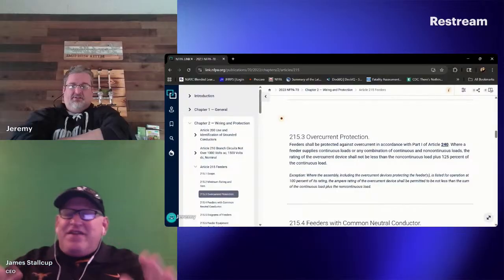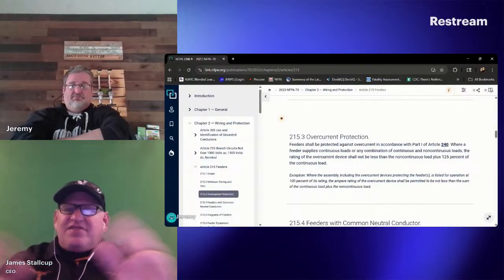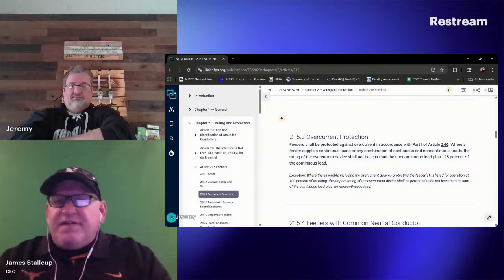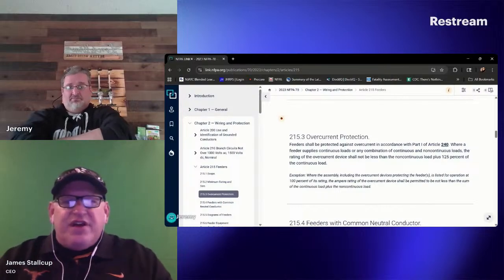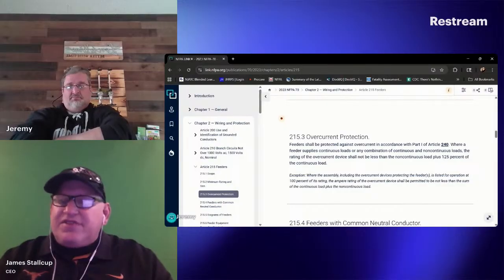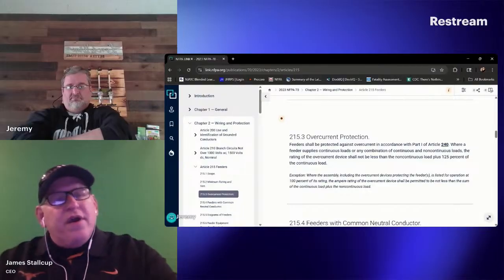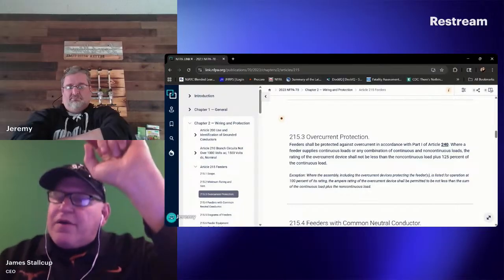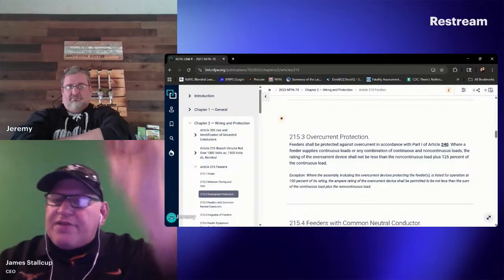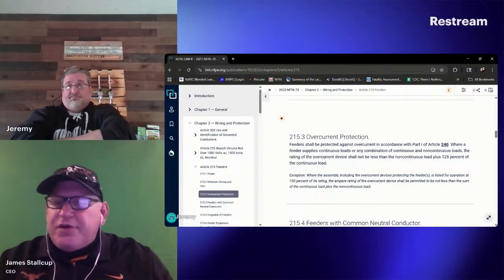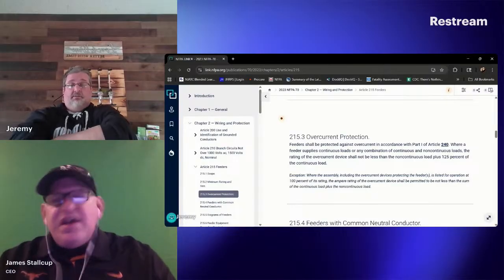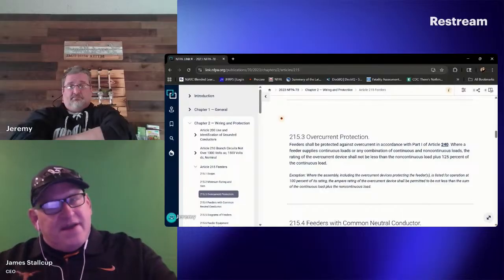Okay, pay attention one more time. When I size the conductors, I'm looking at protection of the conductors here, okay? Once I've sized my conductors, it tells you in 240.4, unless otherwise permitted or required, 240.4(A) through (H). Then you come down and pick your rules up for sizing the overcurrent device. I either go up, if I'm 800 amps or less, I can protect the load or the conductors.